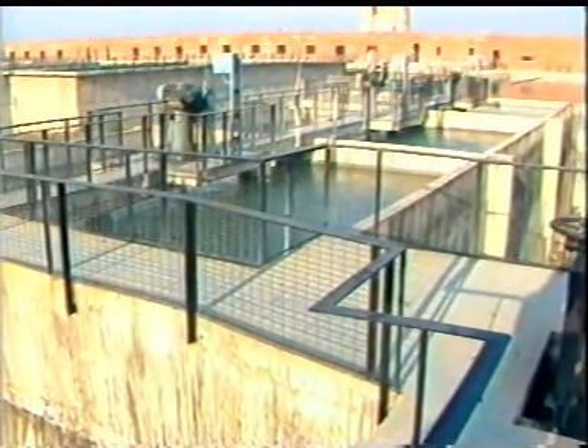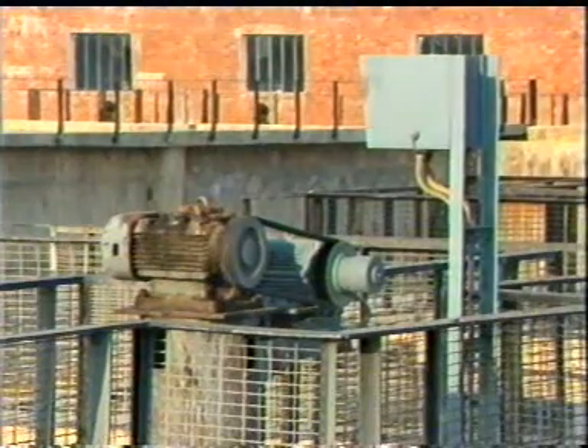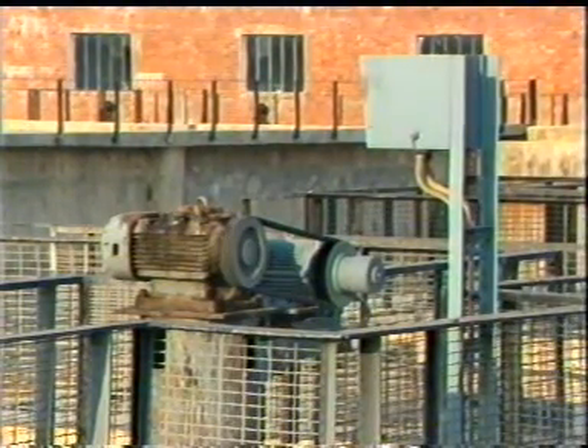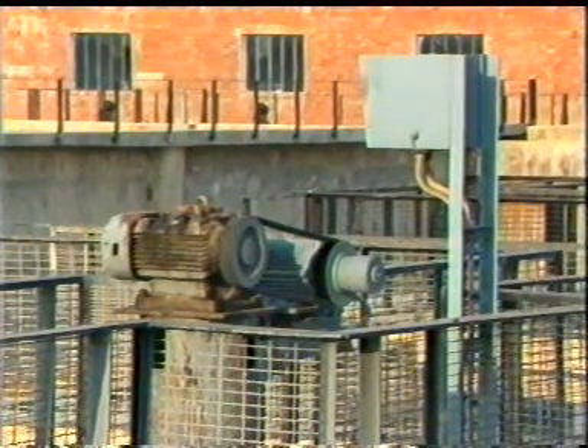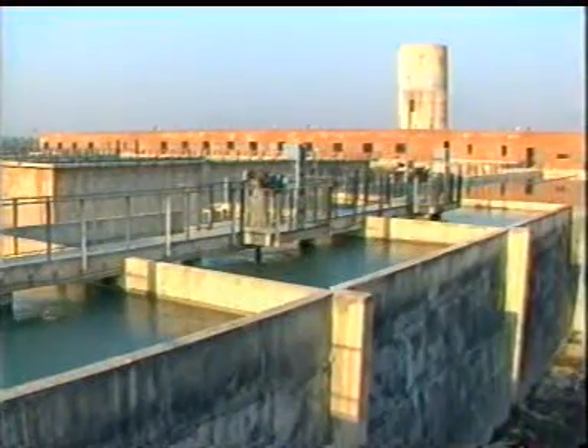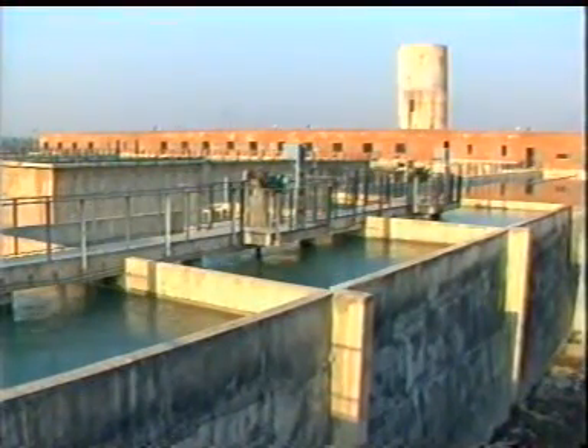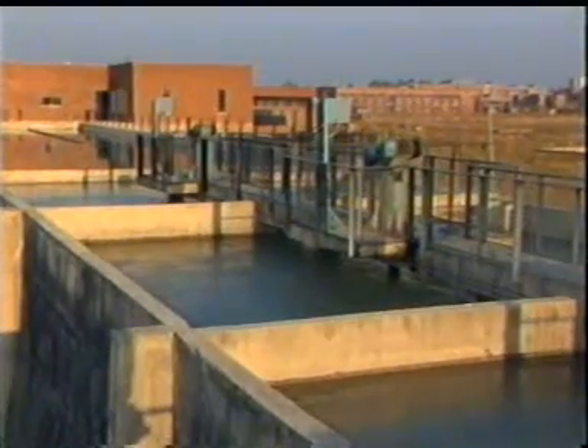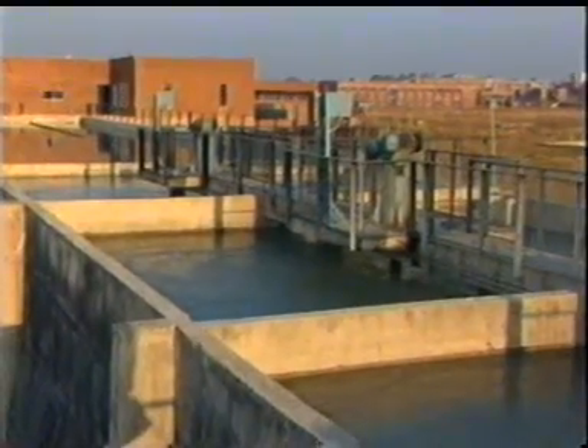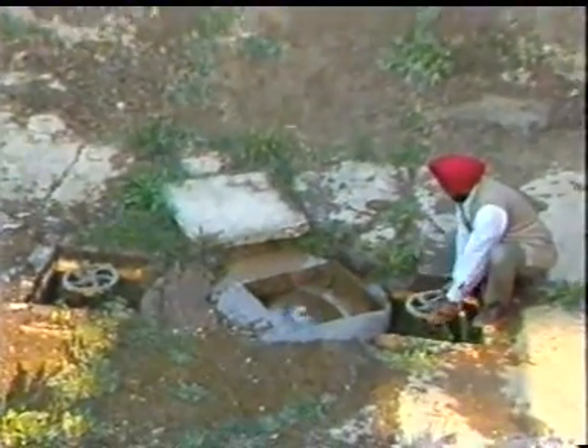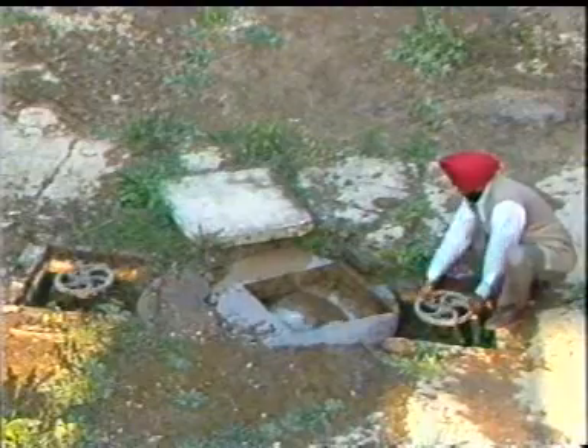In the flocculator, the motor rotates the impeller with blades which agitate the water-alum mix so that flocs can be formed. Heavier flocs get settled down by gravity and are removed by opening the sluice valve provided at the side of the tank.